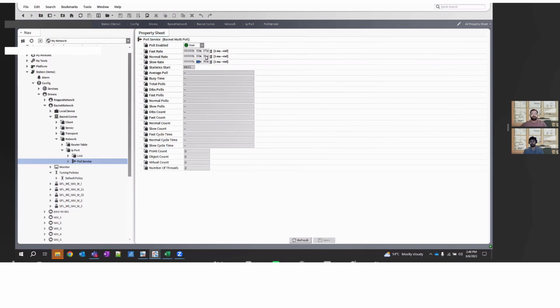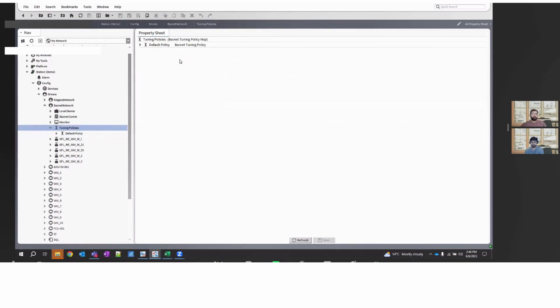The reason I have chosen these numbers is that these are all prime numbers: 7, 31, and 1 minute 30 seconds, which is 90. So there are very few chances that these are going to conflict anywhere. As a starting point, I define these, and then I'll go into the tuning policy under the BACnet network, and what I'll do is duplicate, and name one as fast, the other as slow.